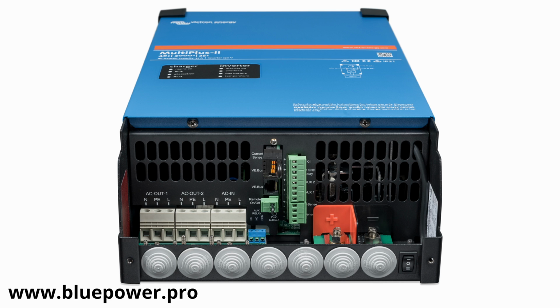What is the capacity of the output 2 then? The one which is directly grid connected? Yeah, so when there's grid available, for 3 kVA you've got 32 amps, for 5 kVA 50 amps, and for 8 up until 15 kVA 100 amps. So 32 amps out on the 2 and 32 amps out on one of the batteries? You're not going to be able to achieve that. So your AC input, one input is going to be limited to 32 amps. Yes. So if your loads are going to be drawing 16 amps, you're only going to have 16 amps available before you reach your limit. So then you're going to only be able to supply 16 amps.